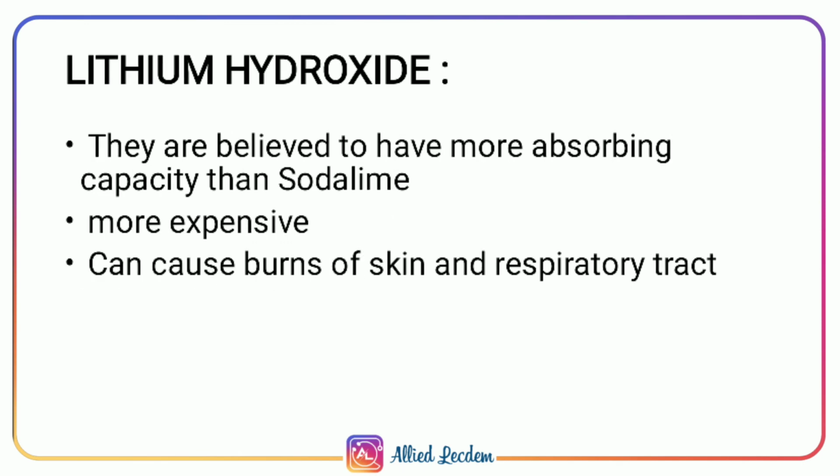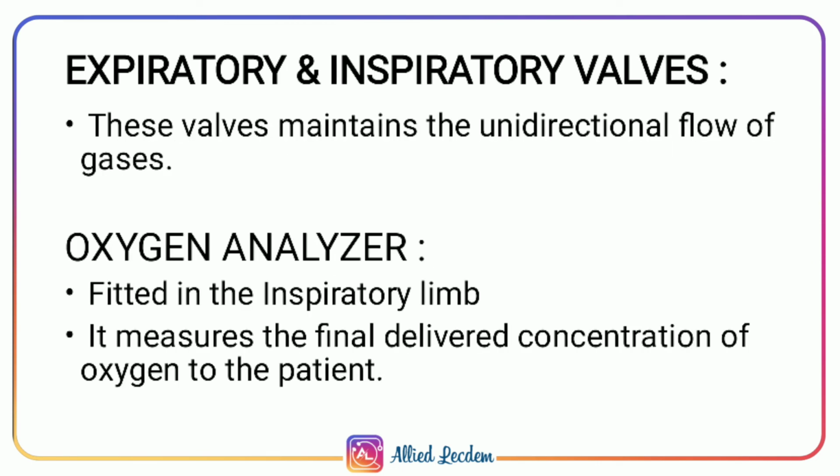And then the next one would be lithium hydroxide. Like Amsorb, lithium based absorbents do not produce compound A. Moreover, they have more absorbing capacity than soda lime, but are very expensive and can cause burns of skin and respiratory tract when inhaled. Now we will see the other components of the closed circuit, the expiratory and inspiratory valves.